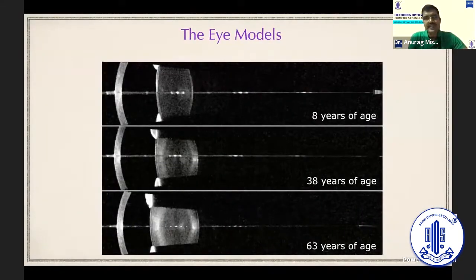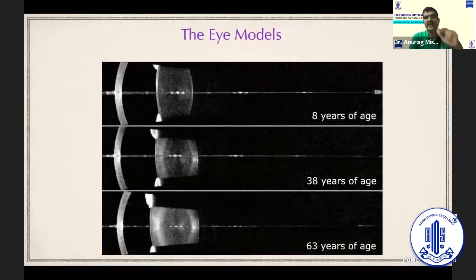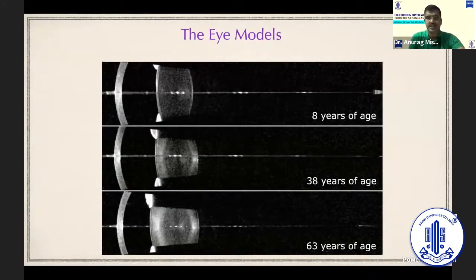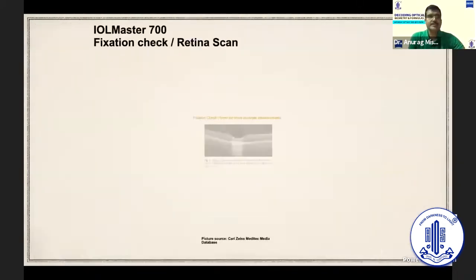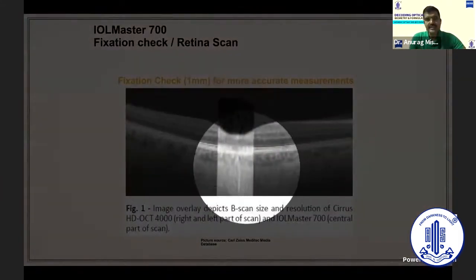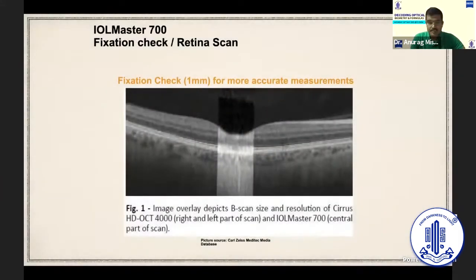The machine has in its database different eye models pertaining to different age groups of the patients. So the moment you punch in the date of birth of the patient in question, it automatically calculates what should be the signal to noise ratio it should employ to calculate the axial length in that particular patient. It also has a fixation check. It takes the center of the fovea, gives us this picture on the screen so that we can cross-check where the light has echoed from. And the central one-millimeter area is where it scans. It takes 256 scans of the same point and repeats it five times. So the accuracy level is very, very high as far as this is concerned.